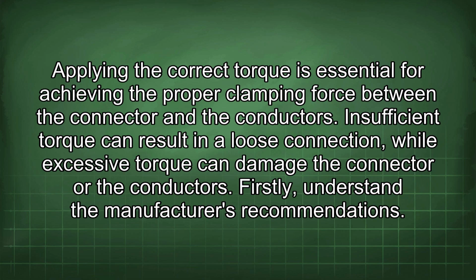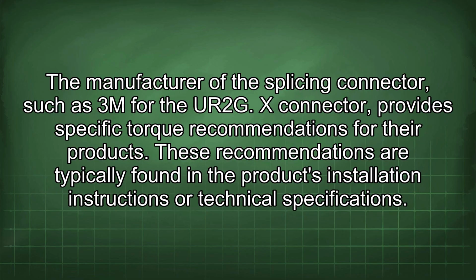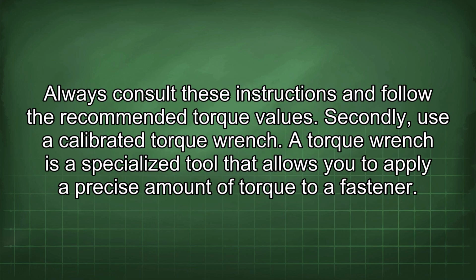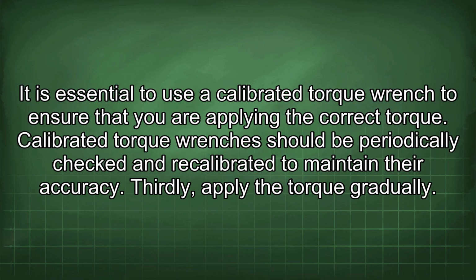Firstly, understand the manufacturer's recommendations. The manufacturer of the splicing connector, such as 3M for the UR2G X connector, provides specific torque recommendations for their products. These recommendations are typically found in a product's installation instructions or technical specifications. Always consult these instructions and follow the recommended torque values. Secondly, use a calibrated torque wrench. A torque wrench is a specialized tool that allows you to apply a precise amount of torque to a fastener. It is essential to use a calibrated torque wrench to ensure that you are applying the correct torque. Calibrated torque wrenches should be periodically checked and recalibrated to maintain their accuracy.